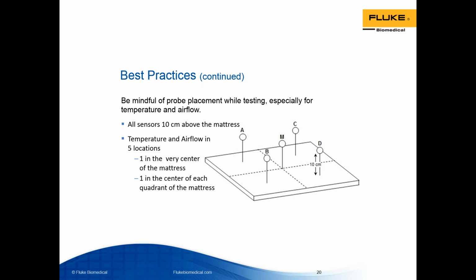temperature. So measuring the temperature and airflow of the incubator in more than one location is going to give a good insight into the actual performance of the medical device, ensuring the uniformity of environmental parameters, because remember that infants cannot self-thermoregulate their temperature. These premature babies cannot. So when a temperature is a little out of range, even in just one corner of the mattress, perhaps where the baby's leg or arm is, because that baby can't self-thermoregulate, that could lead to hypo or hyperthermia or other dire consequences that we touched on earlier.